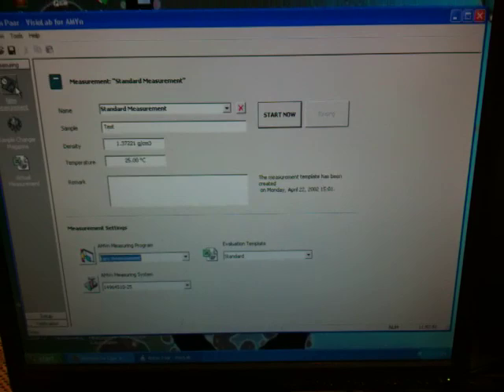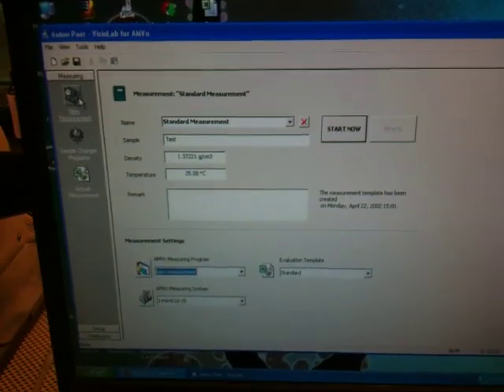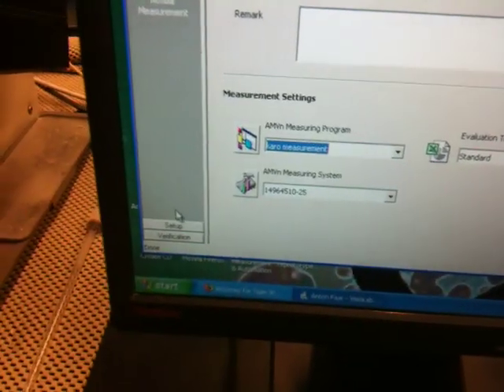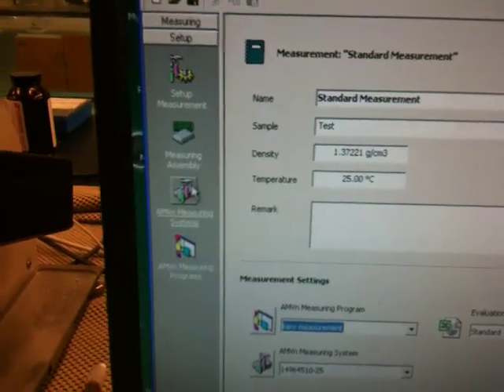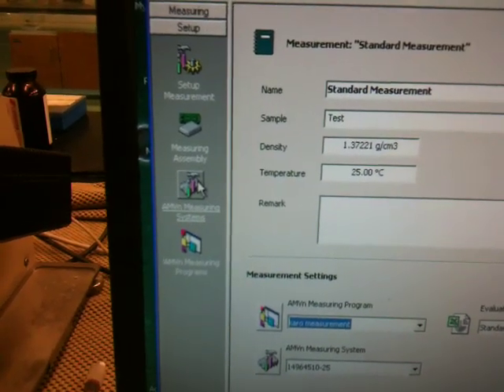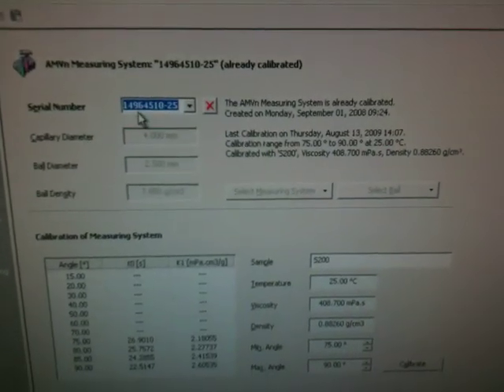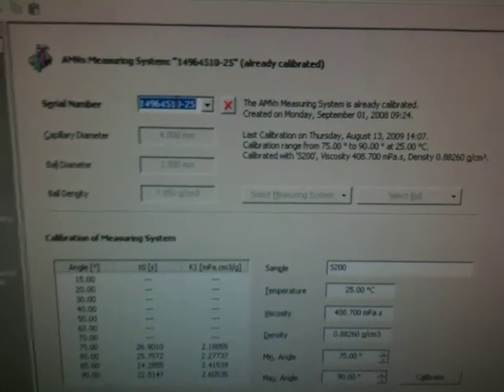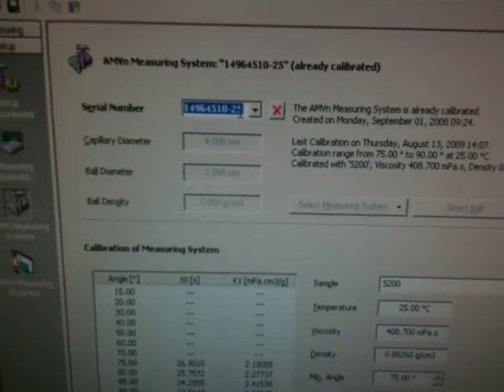On the computer, when you open it up, it's normally here at the new measurements. What you want to do is go down to setup and then do the third one, which is measuring systems. You come up here, you can change this so that you know what capillary it refers to and so that you know the temperature that you're going to use it for.